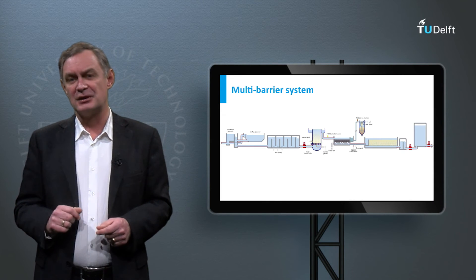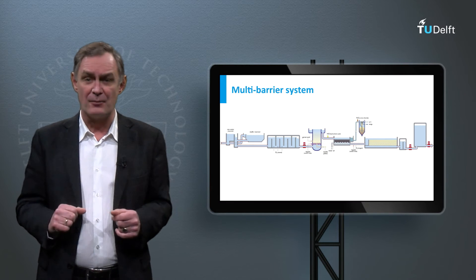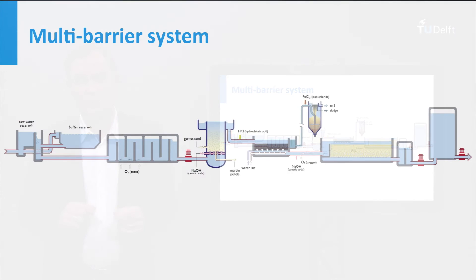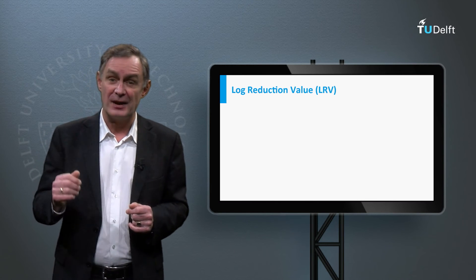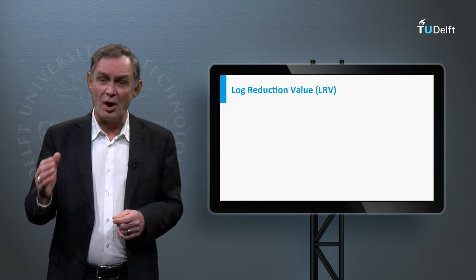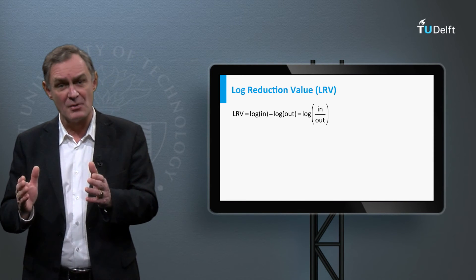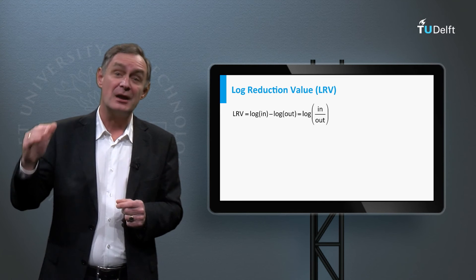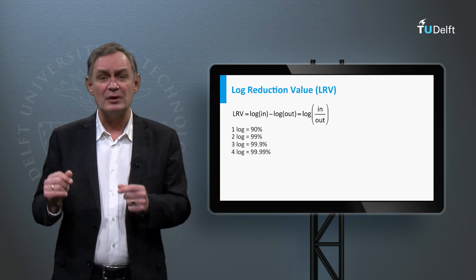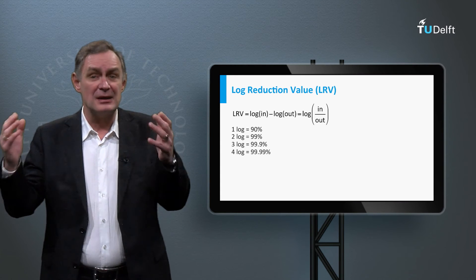To obtain sufficient disinfection in the Netherlands, several types of disinfection methods are placed in series to obtain a more reliable removal of microorganisms. This is what we call a multi-barrier system. In disinfection we generally use the log reduction value, also called the decimal elimination capacity, to express the efficiency of the multi-barrier system. The log reduction value is the logarithm of the incoming concentration minus the logarithm of the outgoing concentration, which is the same as the logarithm of the incoming concentration divided by the outgoing concentration.